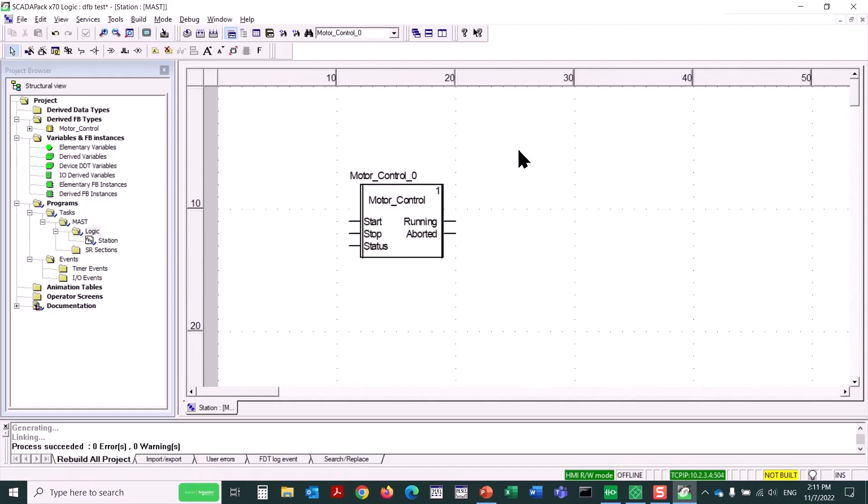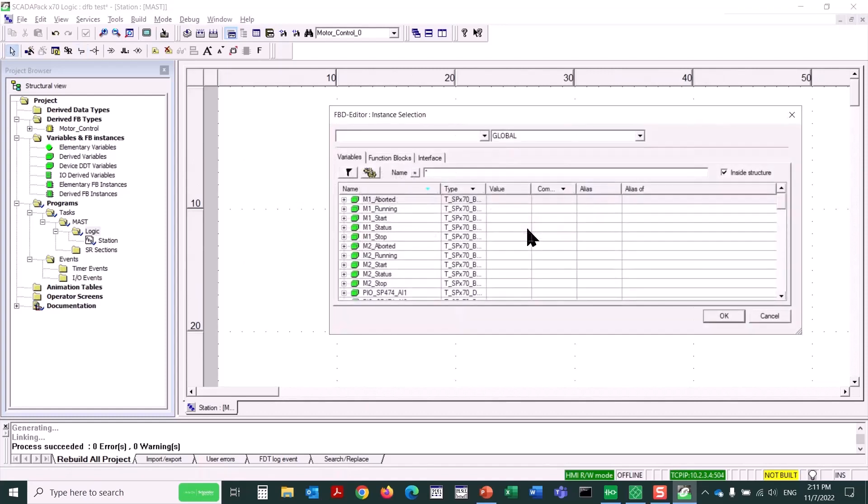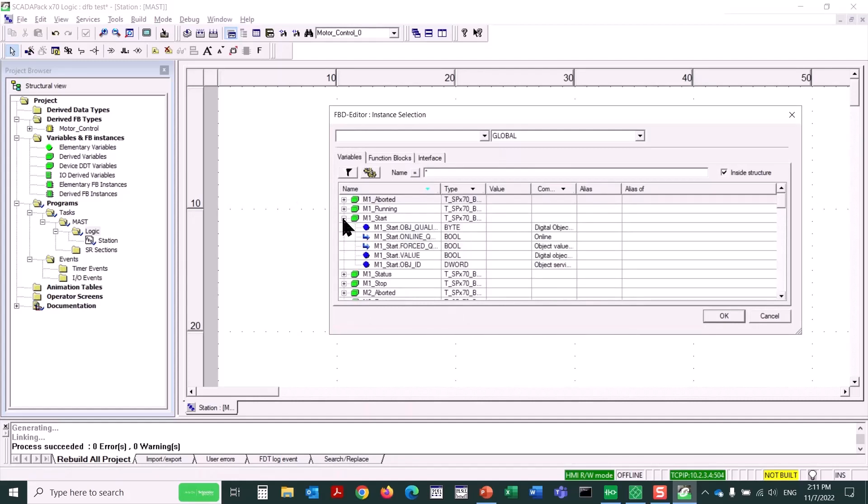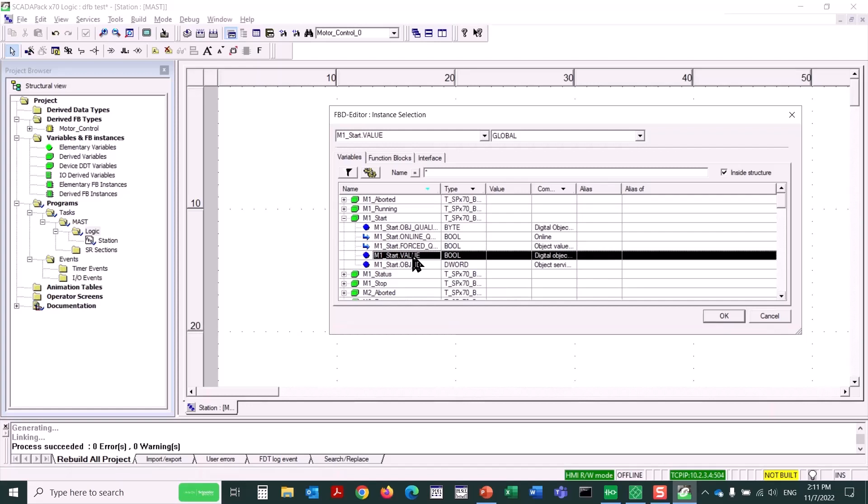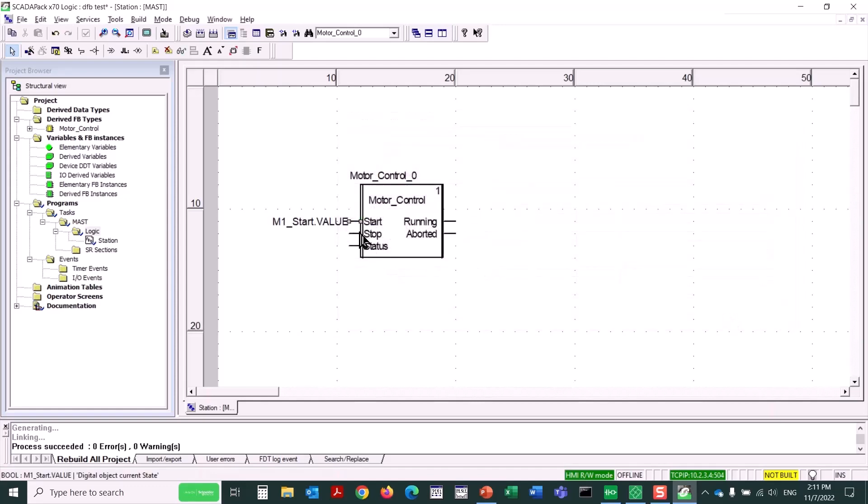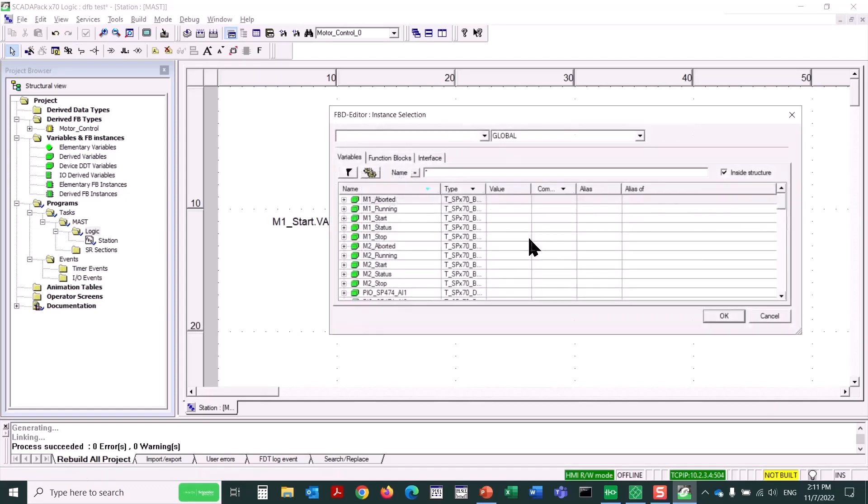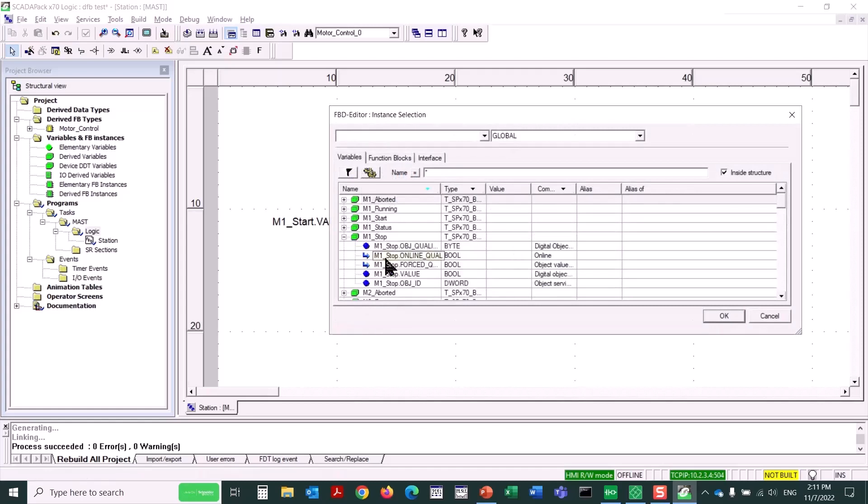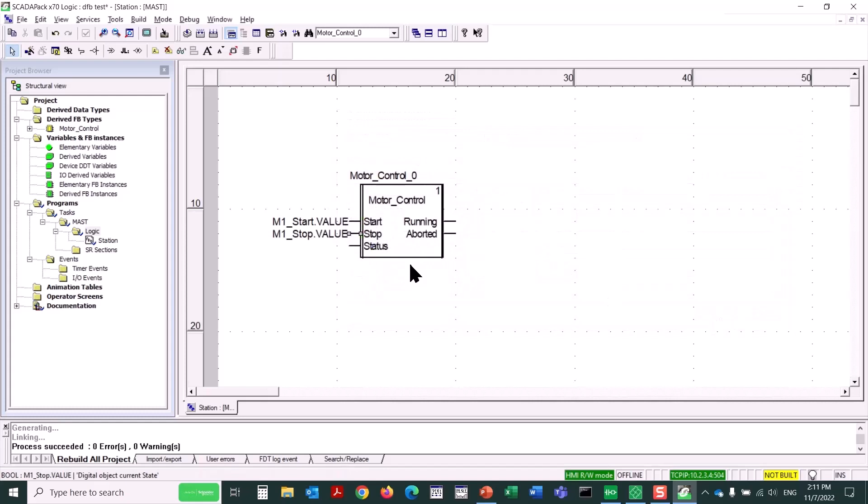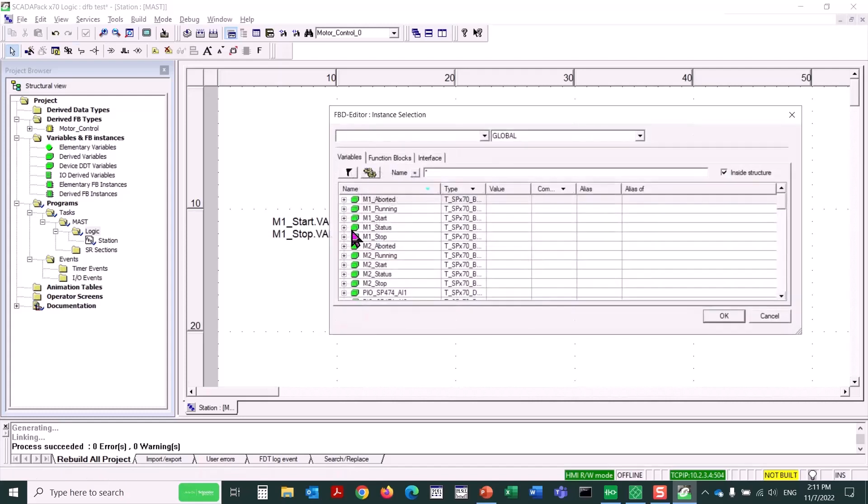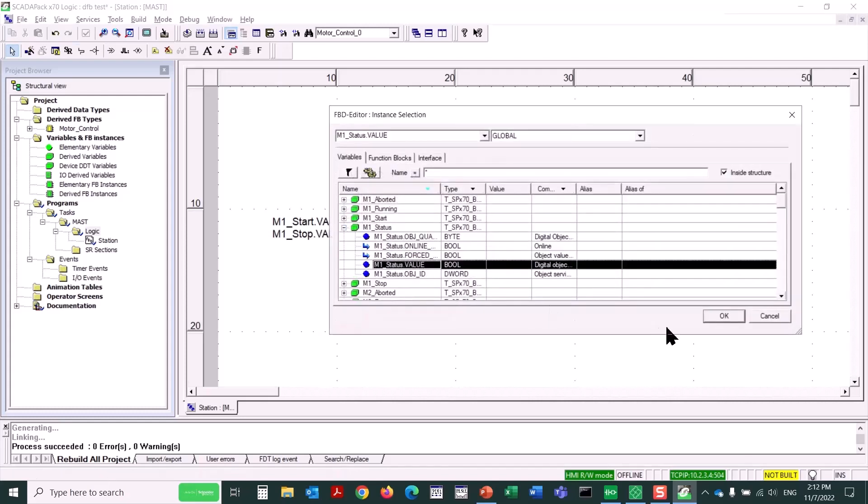OK. So now I'm going to simply double-click on the Start Input pin. Use the Ellipsis button. And I want to pick M1 Start. But not just M1 Start itself. That is the overall object. But we'll click the plus to expand the object. And you can see various parameters. We want the dot value subparameter of this object. Then we'll do the same with stop. And it's going to be M1 stop dot value. And we'll do the same with status. The dot value parameter.